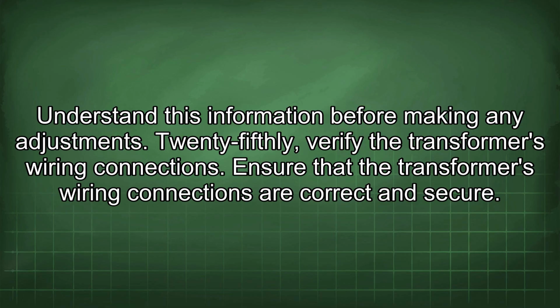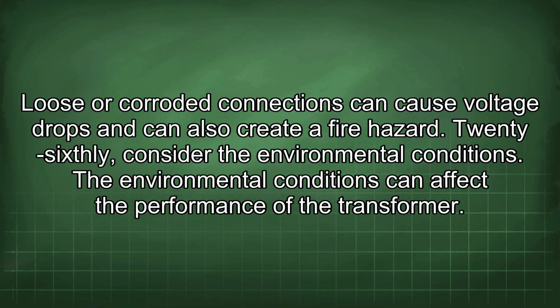25thly, verify the transformer's wiring connections. Ensure that the transformer's wiring connections are correct and secure. Loose or corroded connections can cause voltage drops and can also create a fire hazard.